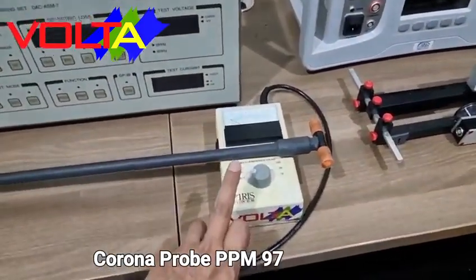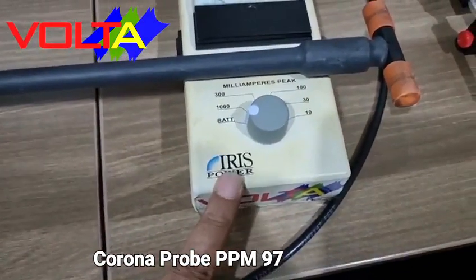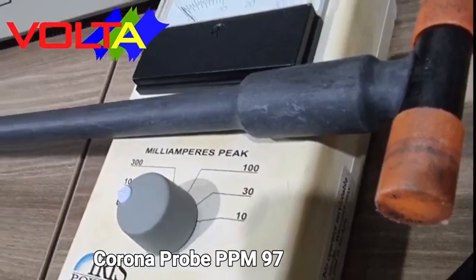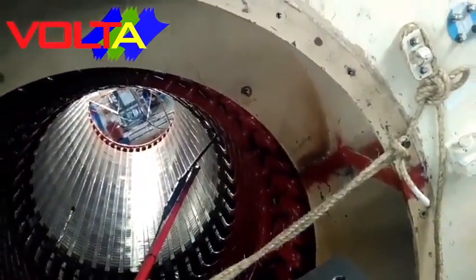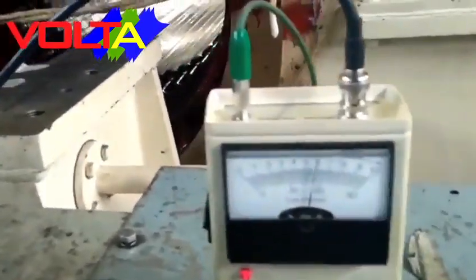The second instrument is the Iris Power Corona Probe PPM 97. During stator winding energized with an external high voltage power supply, by scanning the stator slot, our instrument is able to identify partial discharge activity on every slot. A value more than 20 milliamps for epoxy mica insulation is categorized as high.